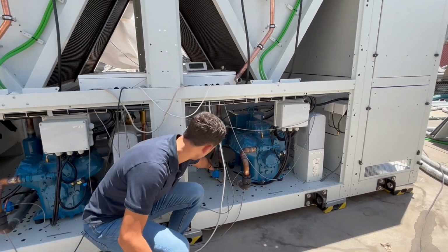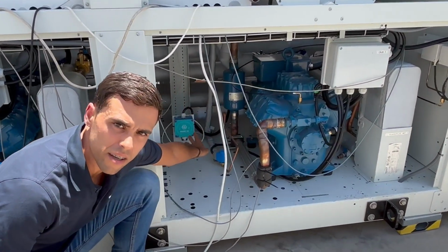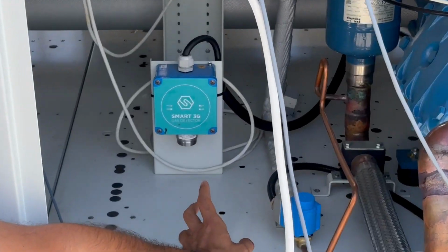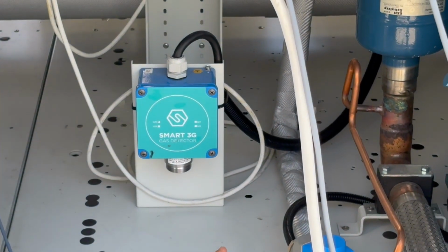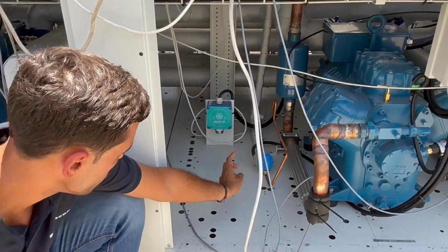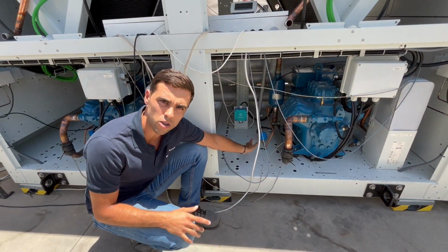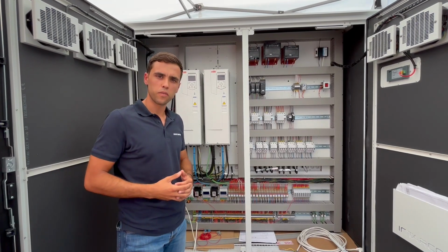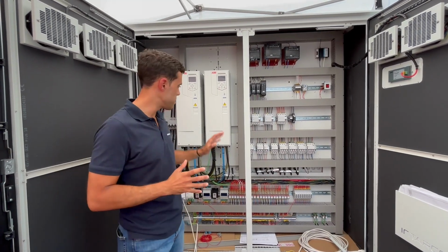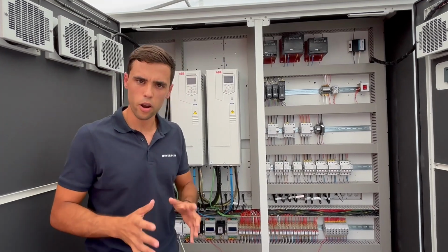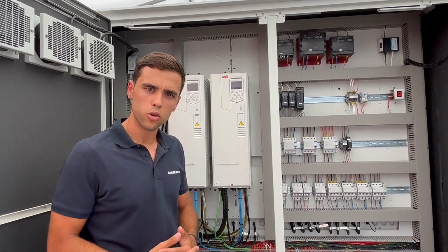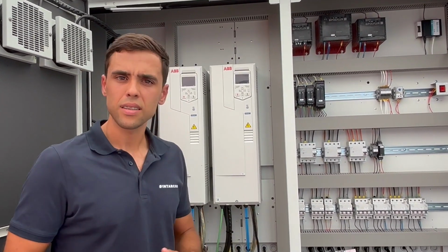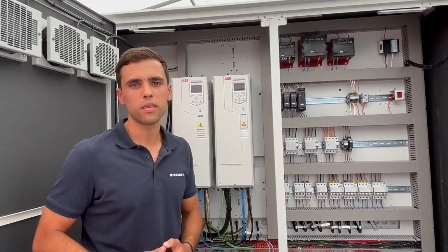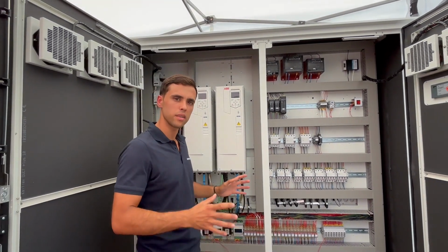On the safety side, we have got a gas leak detector of propane that is in communication with the module that, in case of exceeding a certain level of propane in the air, will cut off the equipment. The key factor of this technology is the use of a VFD, a variable frequency driver, in each compressor. So it allows us to vary the speed according to the demand in each moment.